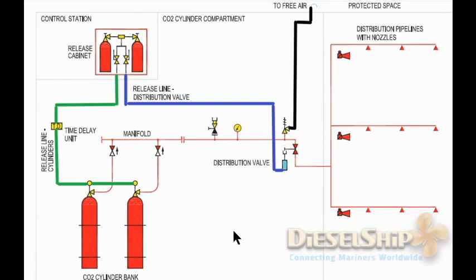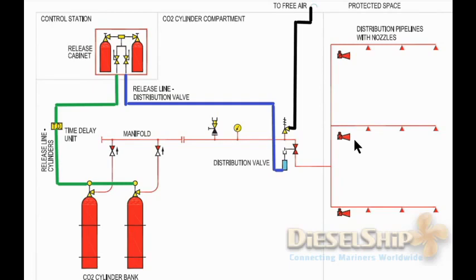Let's see the operation of the system and the major components. For this demonstration I am going to use the protected space as the engine room. We'll consider the engine room is going to be flooded with CO2. We have lots of nozzles distributed all over the engine room, from the bottom platform to the top platform. We have CO2 sounding alarms — visual and audible alarms indicating that CO2 is being flooded inside the engine room. We also have a CO2 room which has the main CO2 bottles; the number totally depends on the gross volume of the engine room.